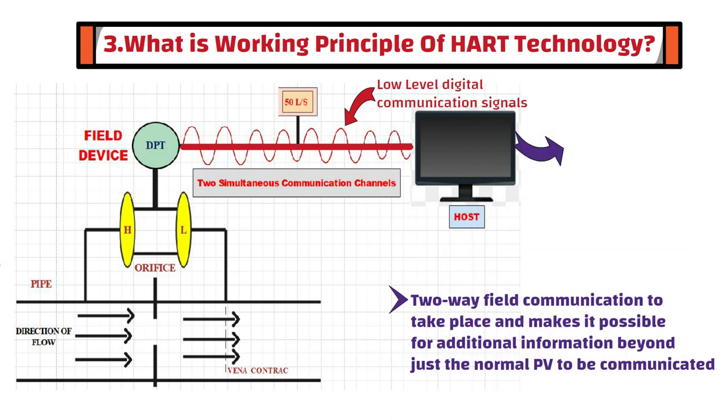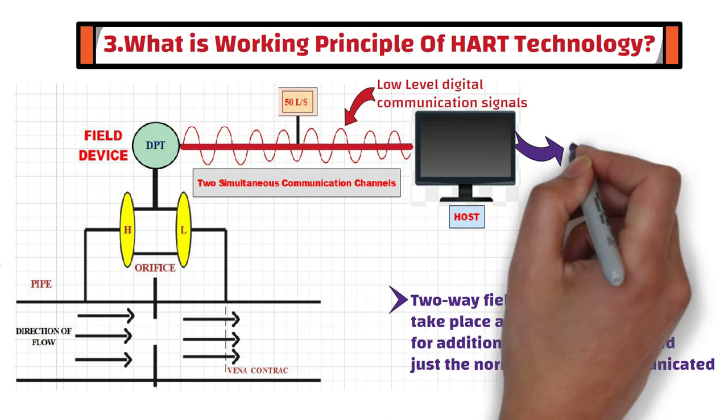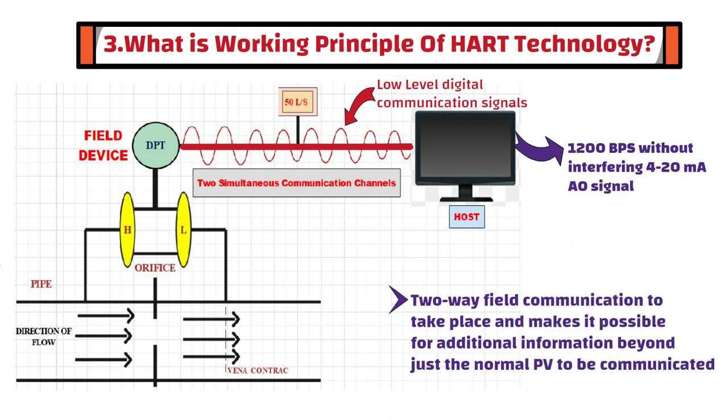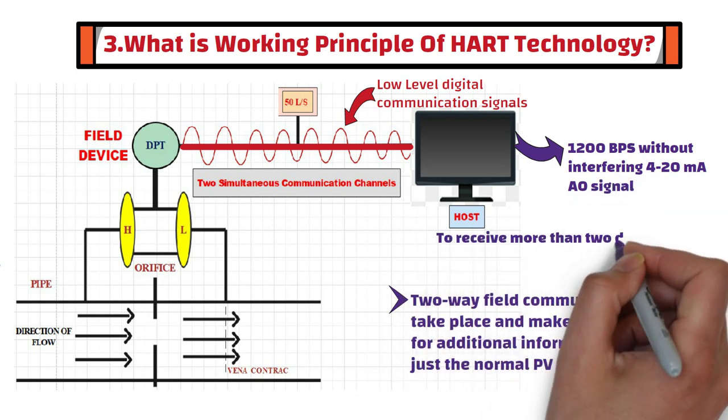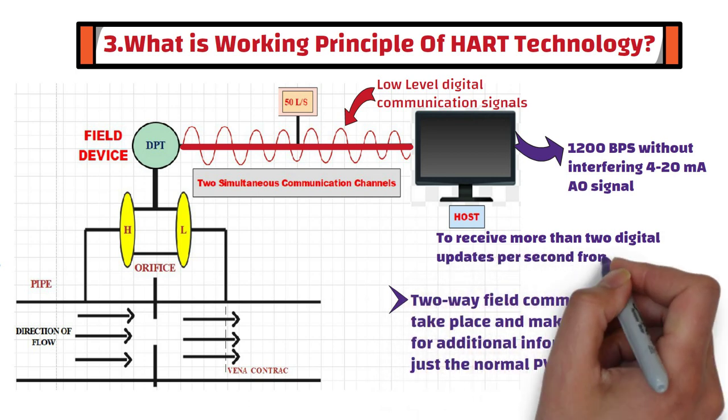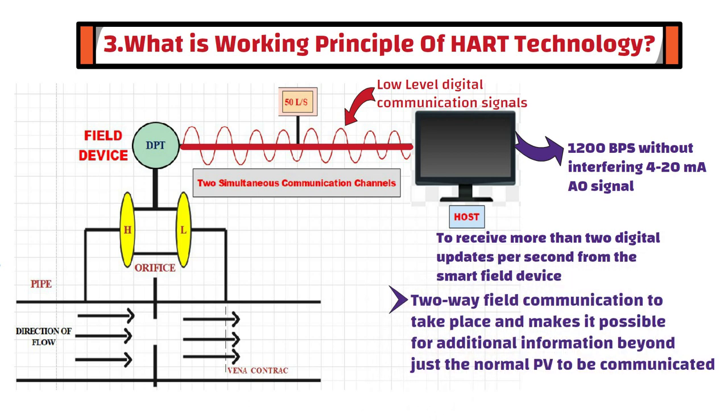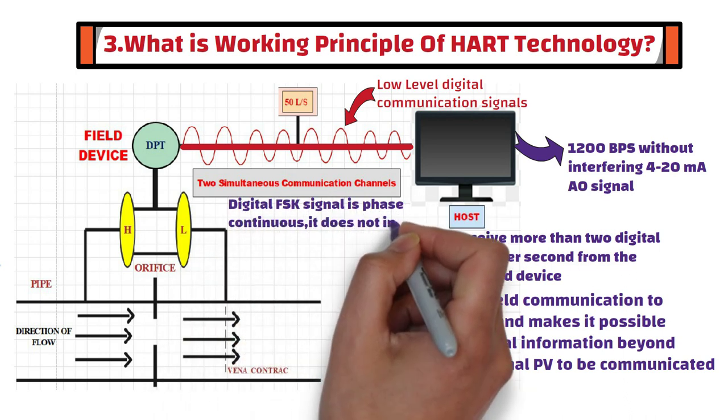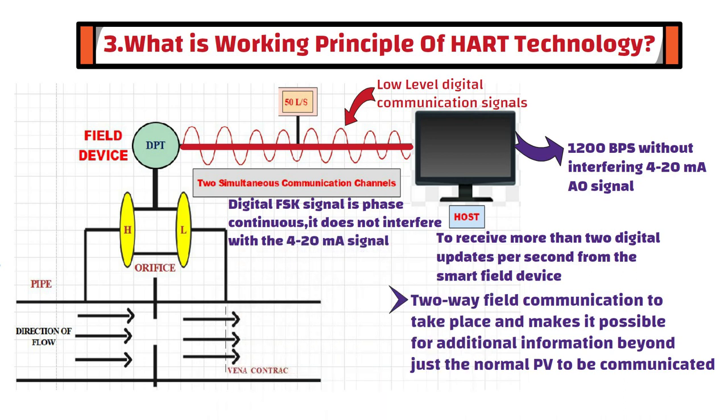In addition to this, the HART protocol communicates at 1,200 bit per second without interfering with 4-20 mA analog signal. This allows the host application to receive more than two digital updates per second from the smart field device. Since the digital frequency shift keying signal is phase continuous, it does not interfere with the 4-20 mA signal.